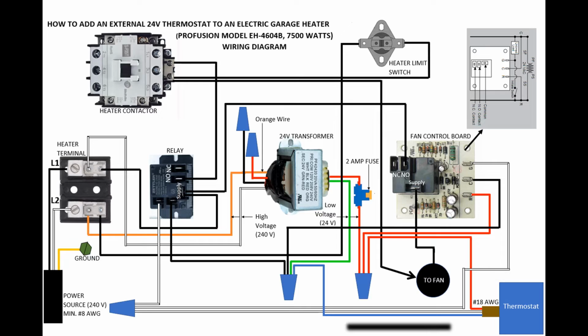Like I said earlier, this fan control board has a built-in delay on make and a delay on break. The way this works, when the thermostat is turned on, the first thing that will happen is that the contactor will close, the heating elements will warm up, and since this board has a delay on make set to 1 second, the fan will turn on after 1 second the coils start to warm up.